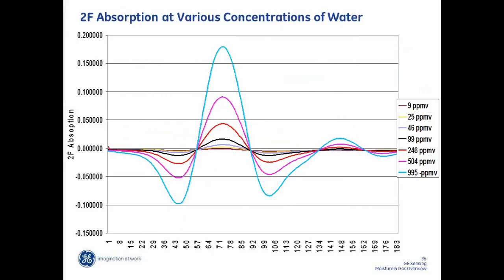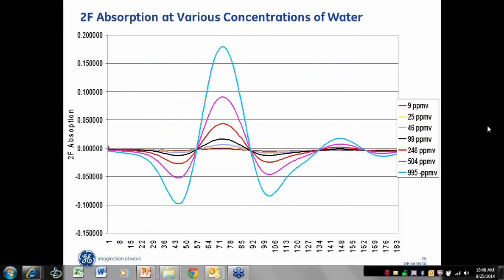This graph just shows the absorption peak at various concentrations, and so we can see that there's a direct proportionality to the height of the peak, centered right around 77 on this graph, and the concentration in parts per million. And this is what's called a 2F or raw signal. So when we calibrate these systems, we're recording that peak height versus the concentration and using that as a lookup table for the system. So one nice thing about this system is it's very, very repeatable.